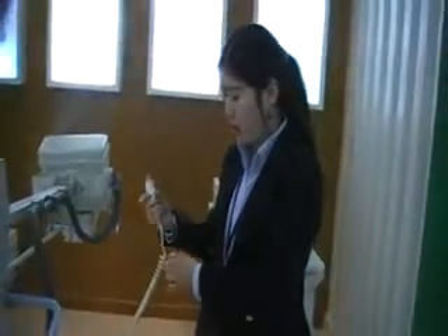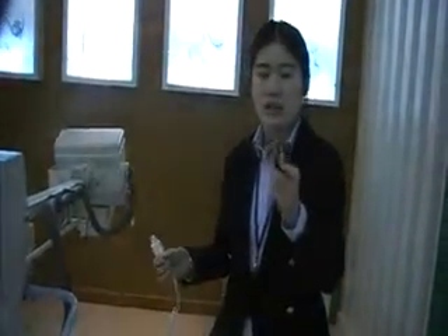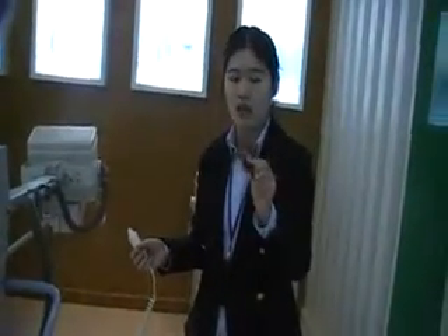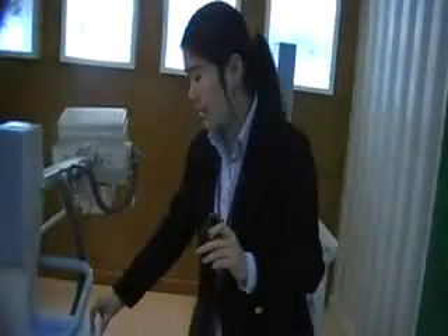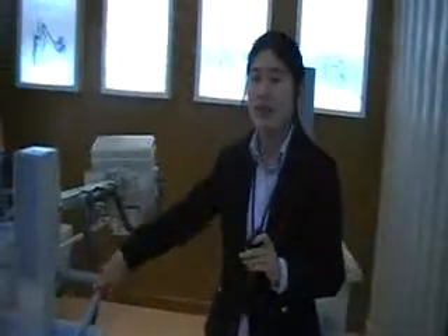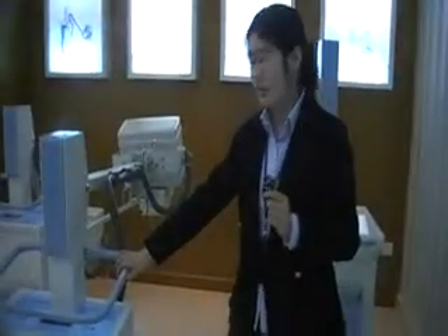And here is the LCD display. We have 50 preset exposure programs for storage or use. And here are the 2 buttons for kV and mAs adjustment. For the exposure, we have 2 control methods. One is the hand switch, and you can also choose to use this. This is a 20-meter wireless remote control for the exposure. When you are at a far distance from the machine, it can protect you from the X-ray exposure.